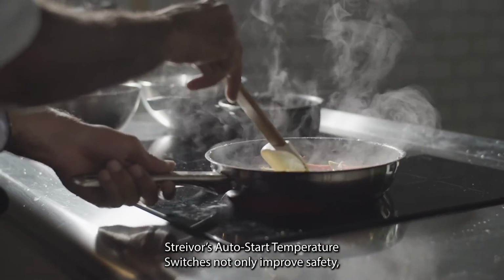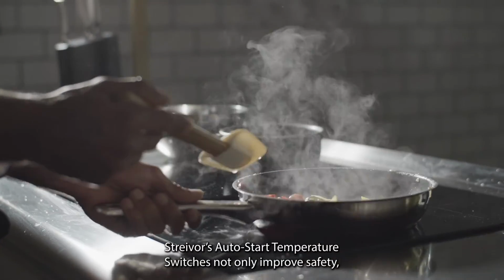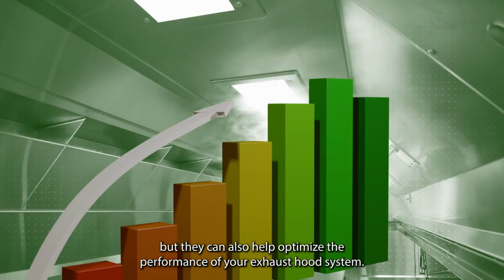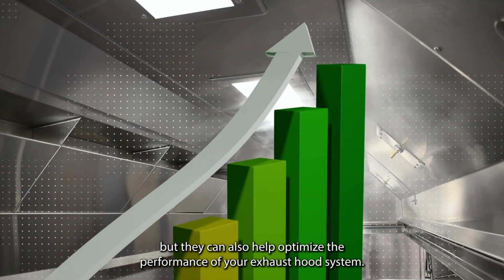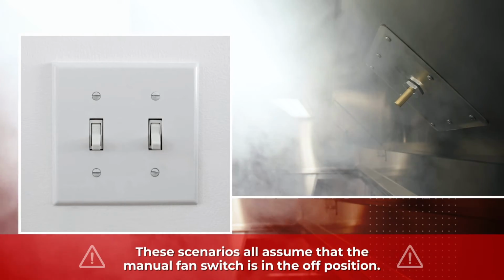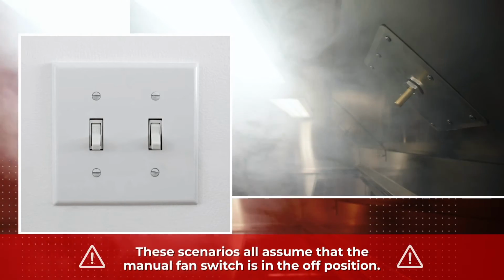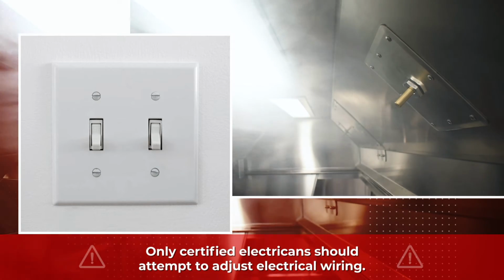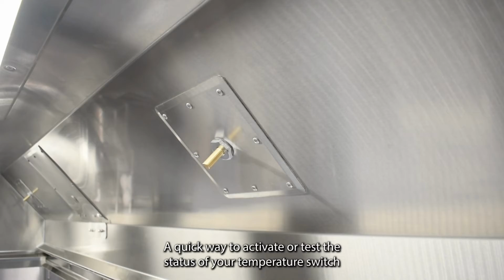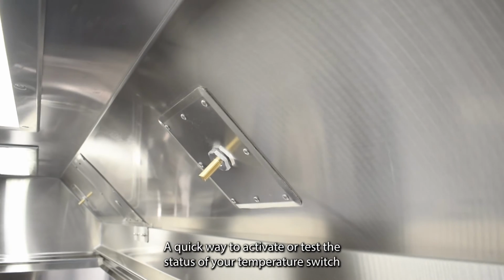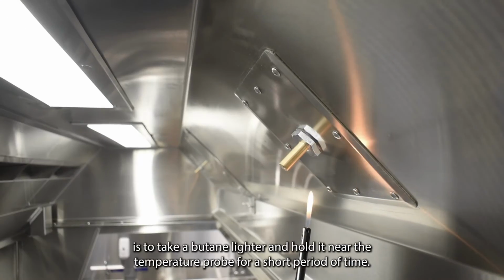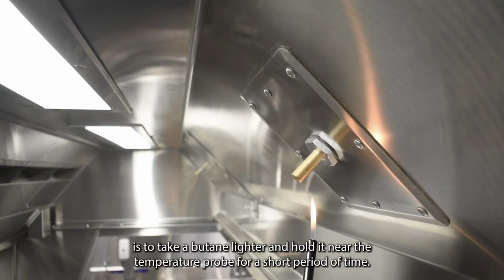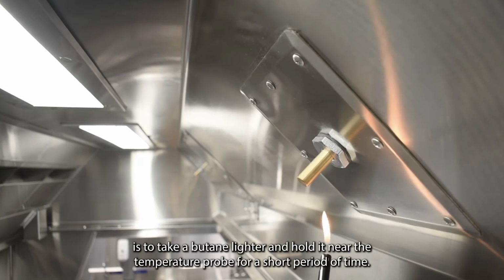Streivor's auto start temperature switches not only improve safety, but they can also help optimize the performance of your exhaust hood system. You may run into a few scenarios which undesirably influence the hood system's performance, but don't worry, we are here to help. A quick way to activate or test the status of your temperature switches is to take a butane lighter and hold it near the switch probe for a short period of time.